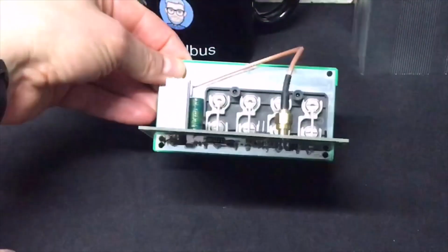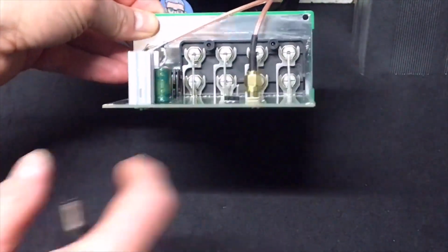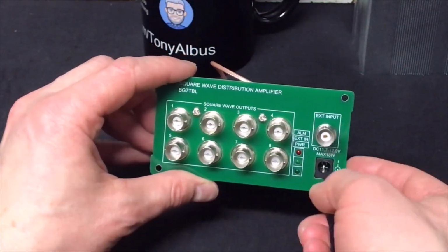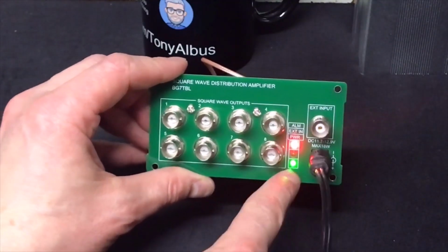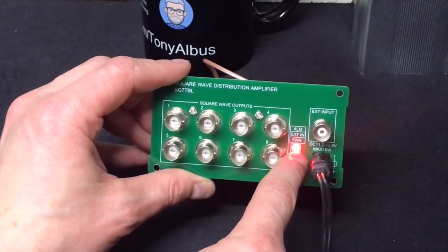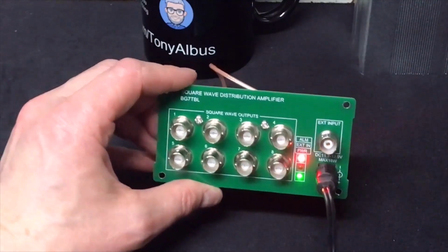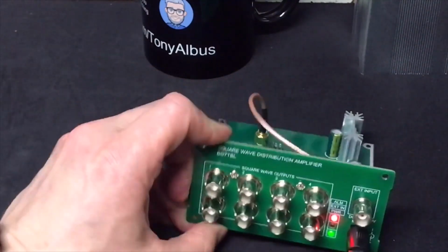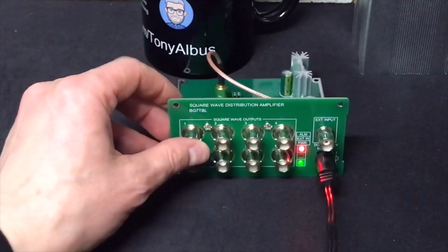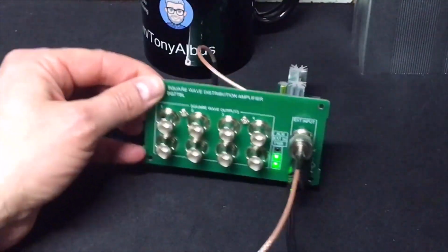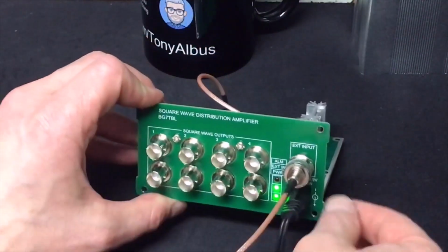Now, of course, I will be using it like this in the back because the wires are all in the back. So I need indication here, and there are 3 LEDs here, but I think 2 is enough because here we have the power and we have the alarm, and the red is the alarm. And the alarm is now on because it doesn't see an input signal. But if we put input, then alarm goes off and the external in goes on.